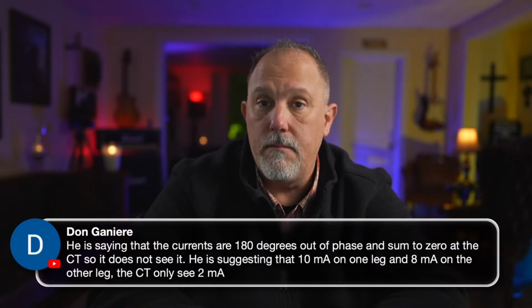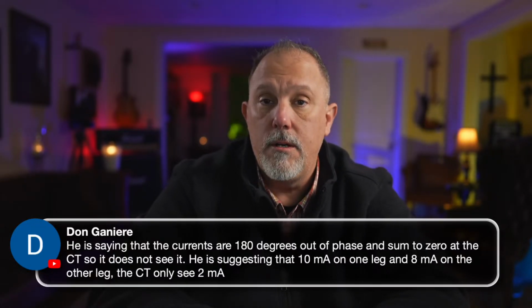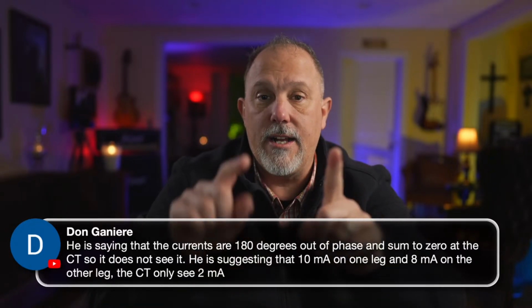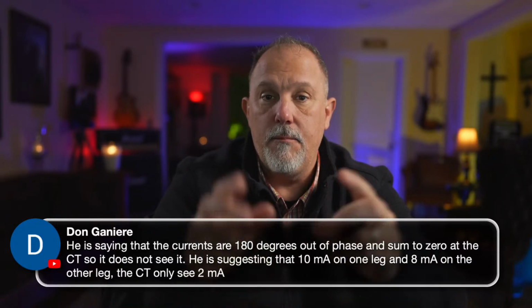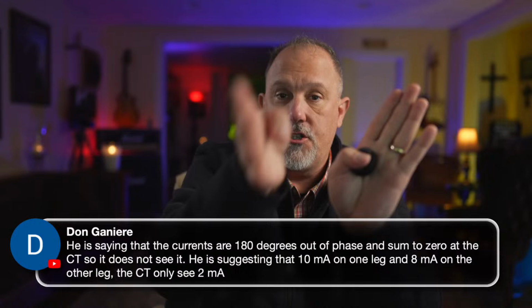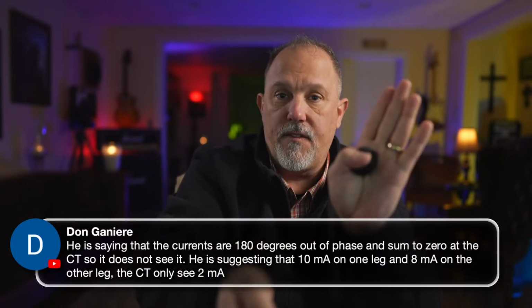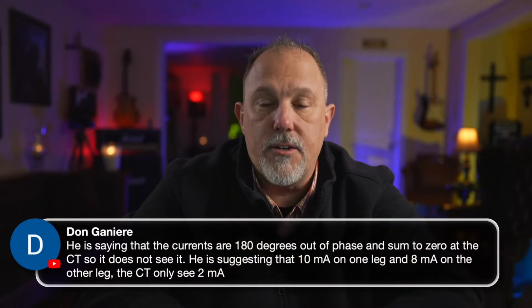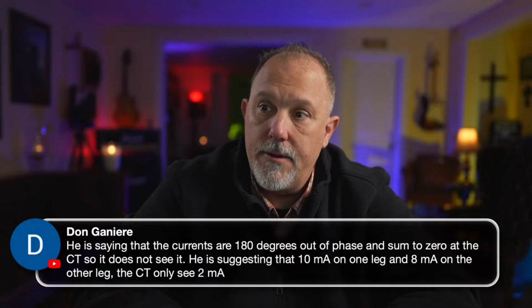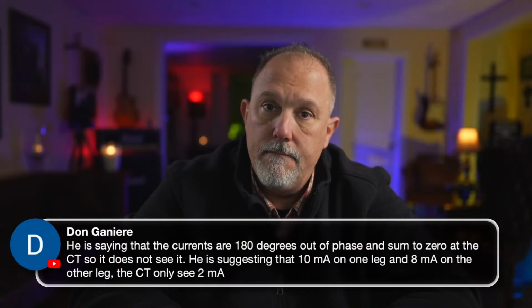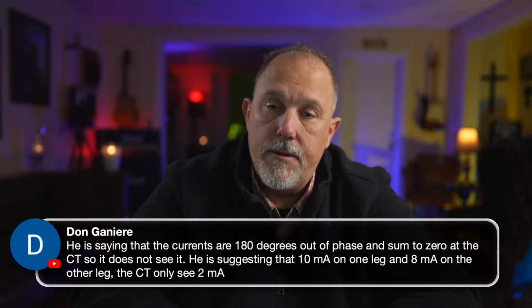The GFCI won't know when I have two hots go into the equipment grounding conductor, because they're out of phase with each other and an amp flows this way and an amp flows that way, it's not going to trip. I don't know that I agree with that, Dawn. I don't know that I agree with that.